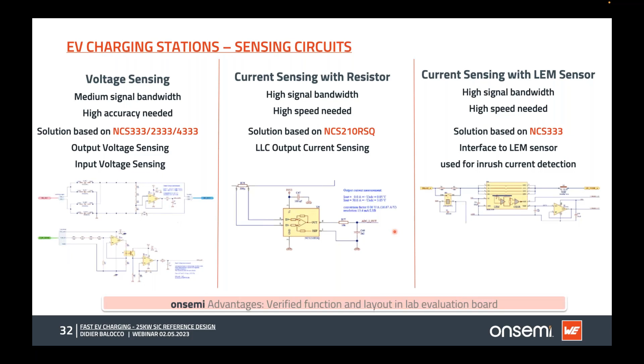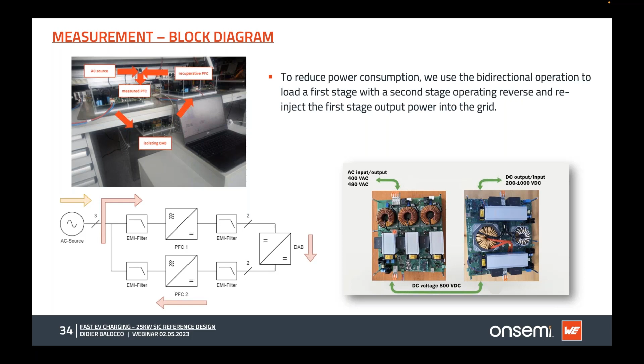For measurement and results now: to avoid losing all the power, we made a loop test, meaning the output voltage is fed back to the input and to the grid, recycling inside this loop. The grid only needs to produce the energy for the losses inside the loop. This way, to test the 25 kilowatt system, we only need 1.5 kilowatt, which corresponds to about 500 watt per board losses at full power. This also allows us to test the bidirectionality of the devices.